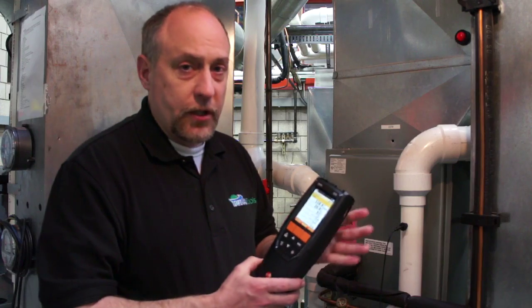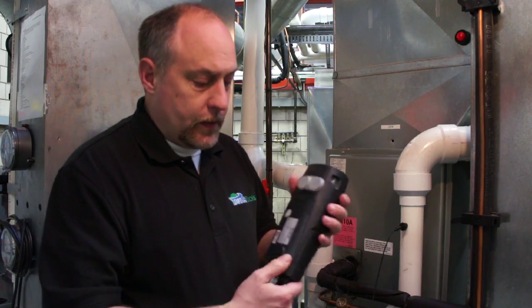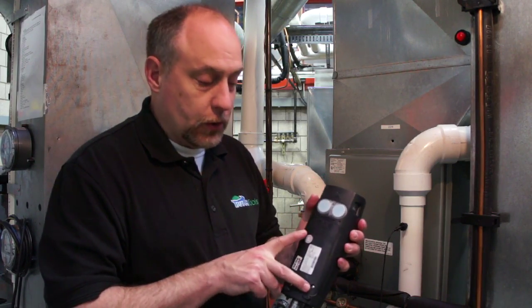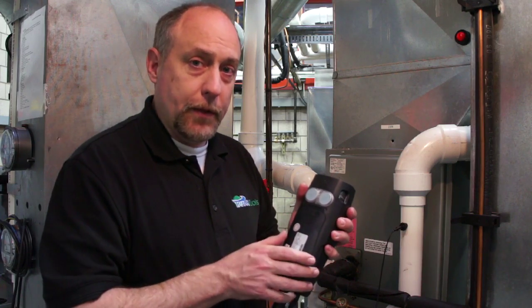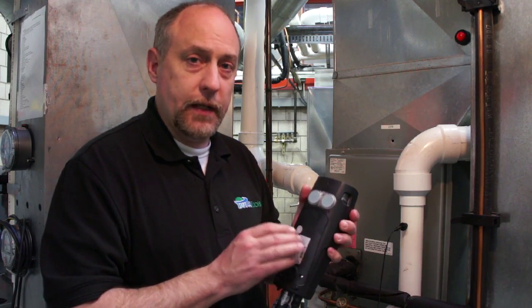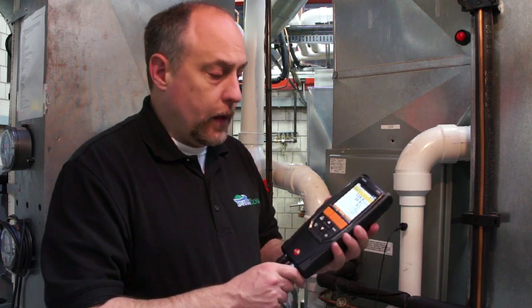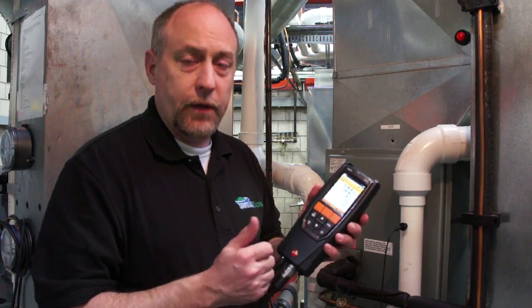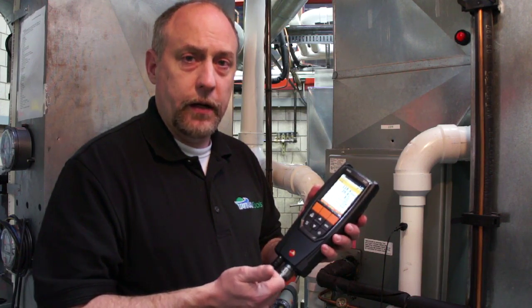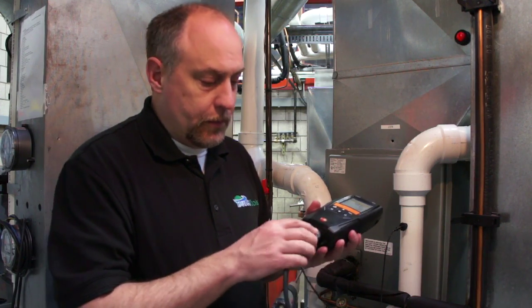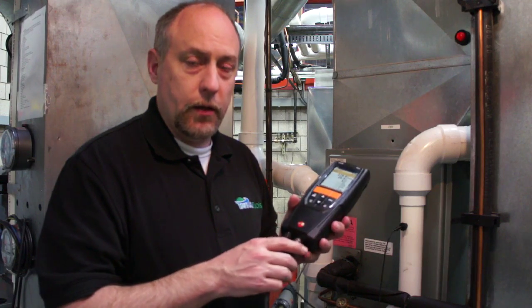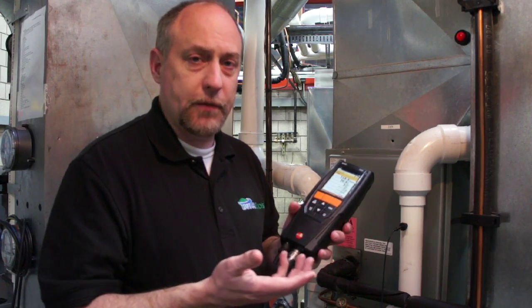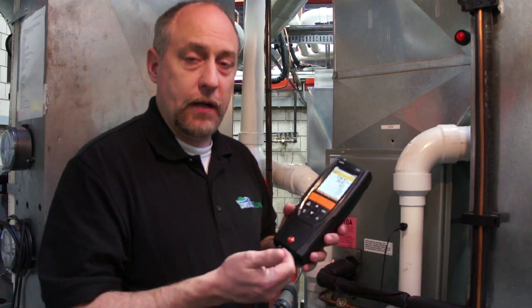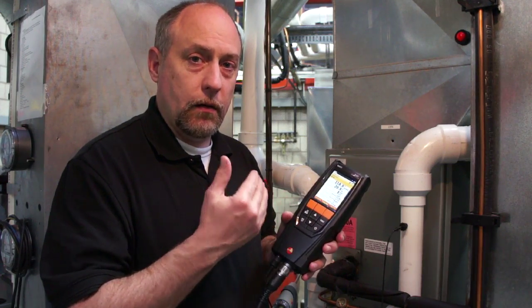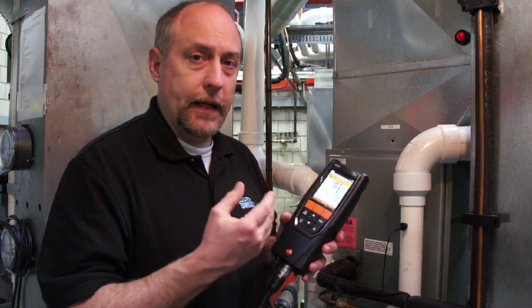A couple other nice features on the 320 are, it does have field replaceable sensors. So a couple screws in the back, pull that out. You can pop a new O2 or CO sensor right in the instrument yourself in a few minutes. The 320 also has firmware that can be upgraded by the user. If you go to the Testo download center, if there's a firmware upgrade, you simply upgrade it through the USB port here. It goes into a boot mode. The directions are right on the website. You simply drag and drop the firmware right into the instrument, and it'll load the new firmware for you, and it's good to go.